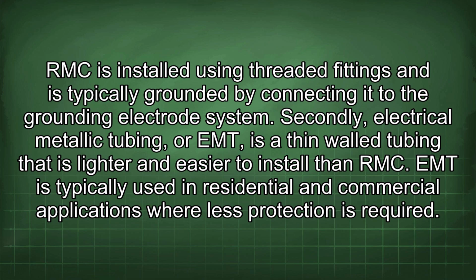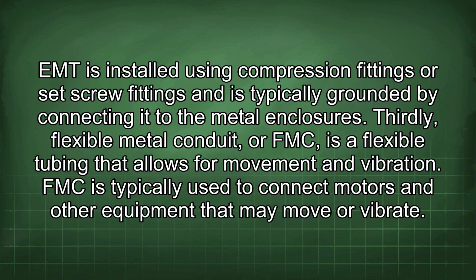Secondly, electrical metallic tubing, or EMT, is a thin-walled tubing that is lighter and easier to install than RMC. EMT is typically used in residential and commercial applications where less protection is required. EMT is installed using compression fittings or set screw fittings and is typically grounded by connecting it to the metal enclosures. Thirdly, flexible metal conduit, or FMC, is a flexible tubing that allows for movement and vibration.